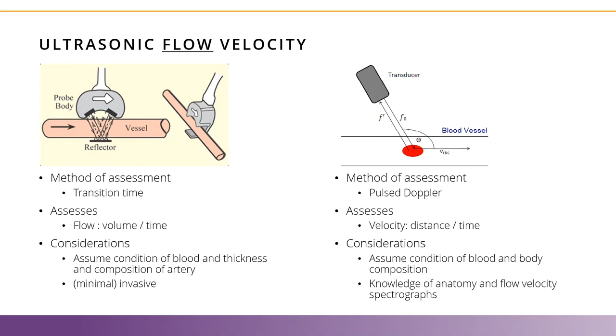And I say flow velocity measurement because the blood will flow through, ultrasound will refract through the measurement angles, and based on that there will be a calculation, and it will give you an amount of blood flow through that specific artery during that measurement time. Whilst on the right side, you have a non-invasive Doppler flow velocity probe measuring flow velocity in a non-invasive way. Both have an assumption on the composition of the blood and the composition of the artery, or in the old Doppler flow velocities, even an assumption on the composition of the body. That has to be kept in mind.